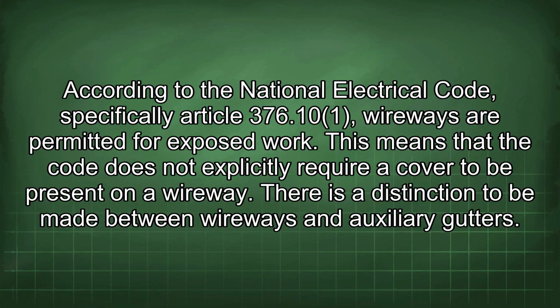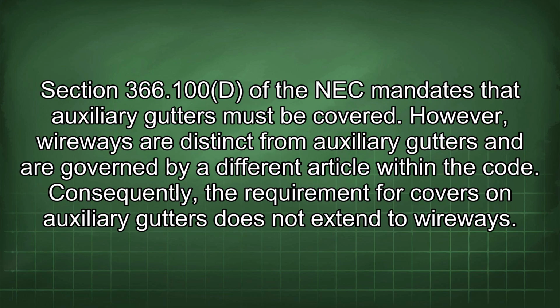There is a distinction to be made between wireways and auxiliary gutters. Section 366.100(D) of the NEC mandates that auxiliary gutters must be covered. However, wireways are distinct from auxiliary gutters and are governed by a different article within the code. Consequently, the requirement for covers on auxiliary gutters does not extend to wireways.